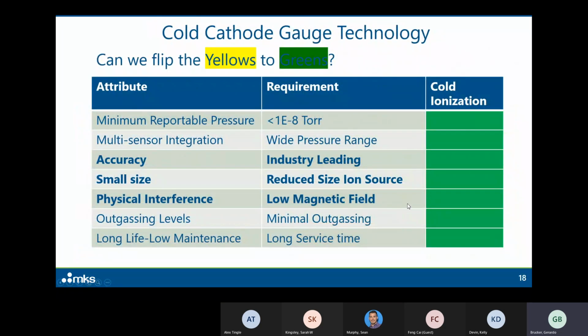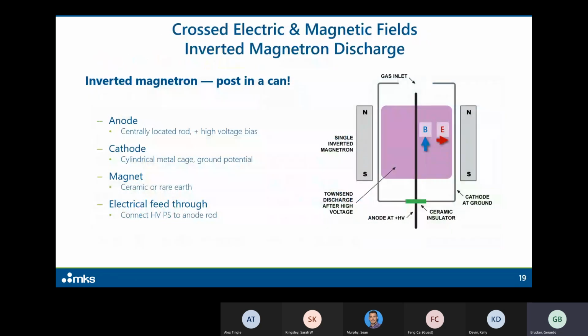So as we moved on, deciding what we're going to do with the 900 series, the first question we asked ourselves was, can we flip these yellows for cold cathode gauge technology into greens, turn everything into greens, right, and provide a modular cold cathode gauge with a 10 to the minus 8 torr minimum reportable pressure, a very wide pressure range through sensor integration, industry-leading accuracy, the smallest ion source design of its kind, a low magnetic field that wouldn't interfere with analytical measurements, and at the same time give you the advantage of low outgassing and long service time. So that's the challenge that we had to go through.